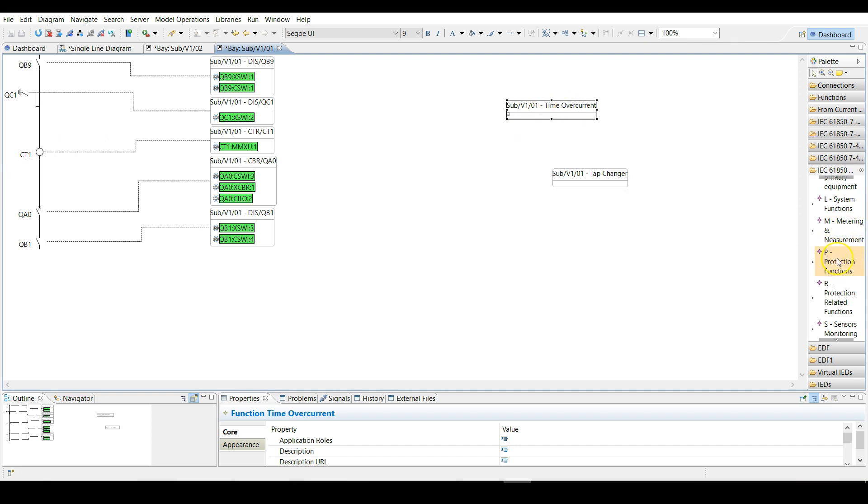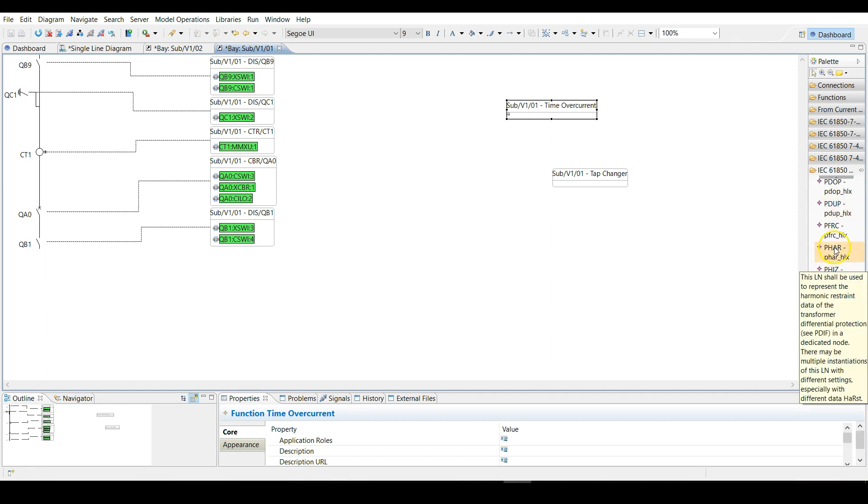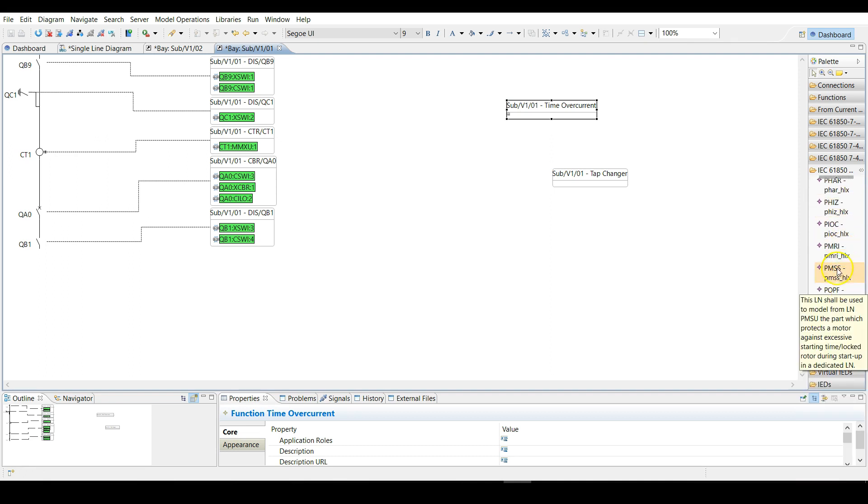For time overcurrent you can go to protection functions logical node and choose PTOC, which is time overcurrent, and PTRC, which is the protection trip condition.